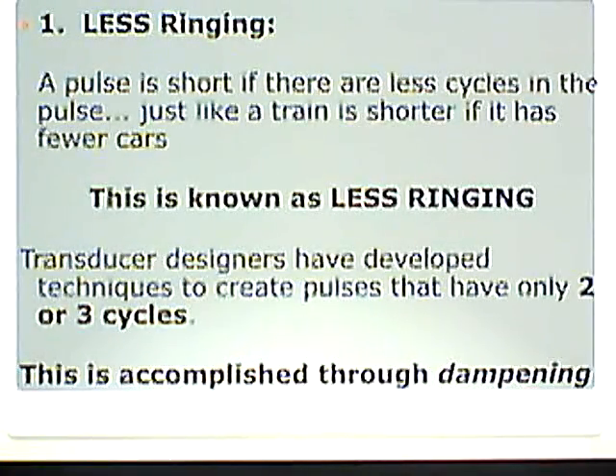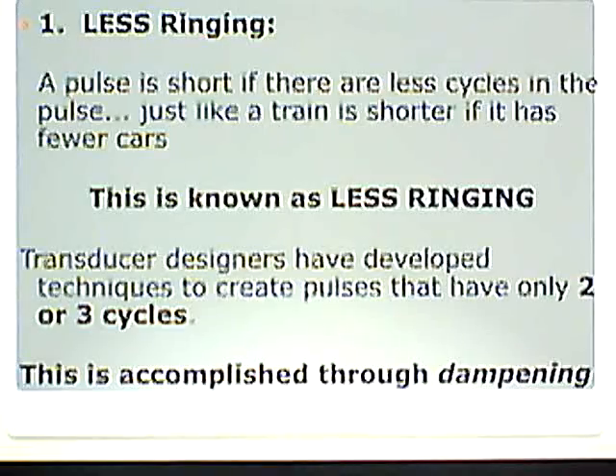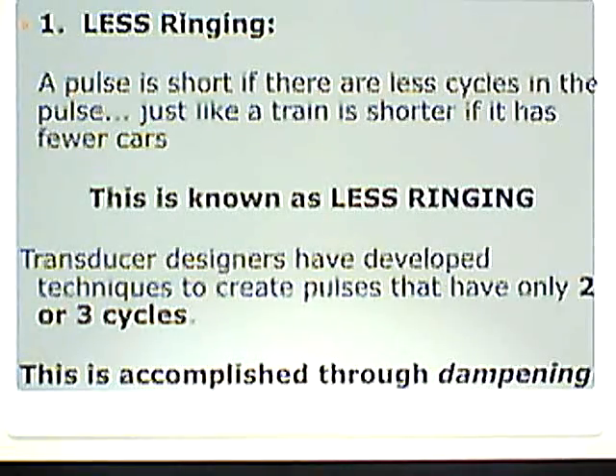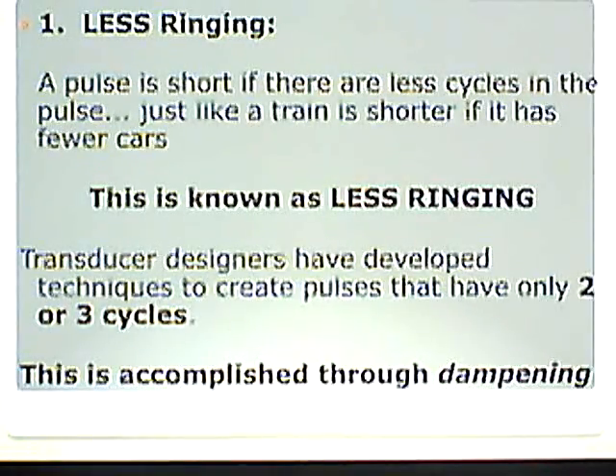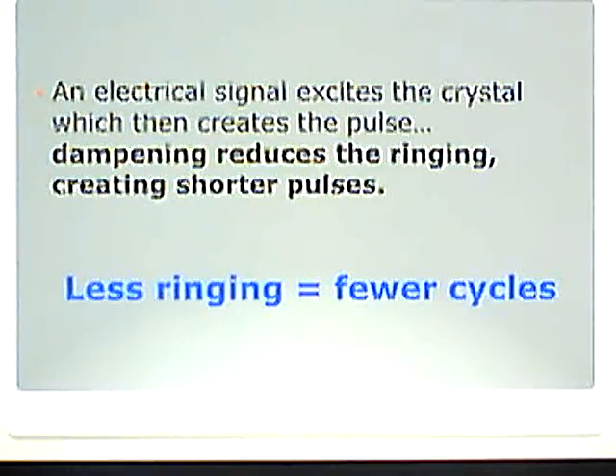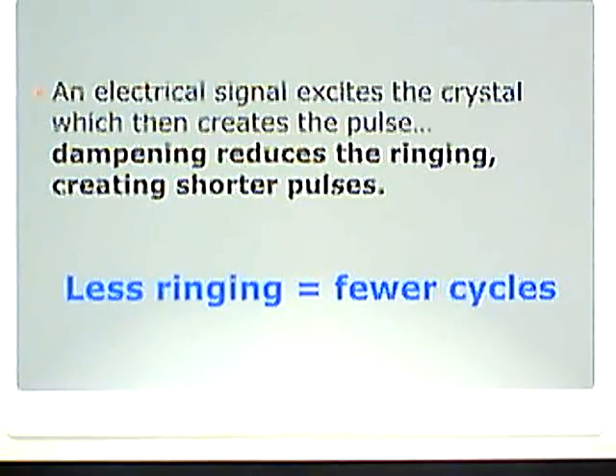Less ringing: a pulse is short if there are fewer cycles in the pulse, just like a train is short if it has fewer cars. This is known as less ringing. Transducer designers have developed techniques to create pulses with only two or three cycles through a process called dampening — like hitting a triangle and then stopping it with your hand to prevent it from ringing. An electrical signal excites the crystal, which creates the pulse. Dampening reduces ringing, creating shorter pulses: less ringing equals fewer cycles.